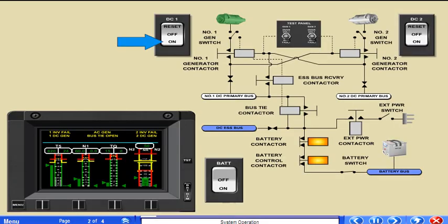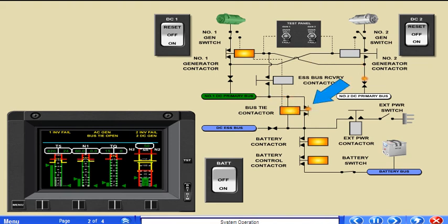With either generator and the battery on, the selected generator powers all DC buses. The bus tie closes automatically and the bus tie open message extinguishes. The selected generator charges the battery. External power is isolated from the electrical system.